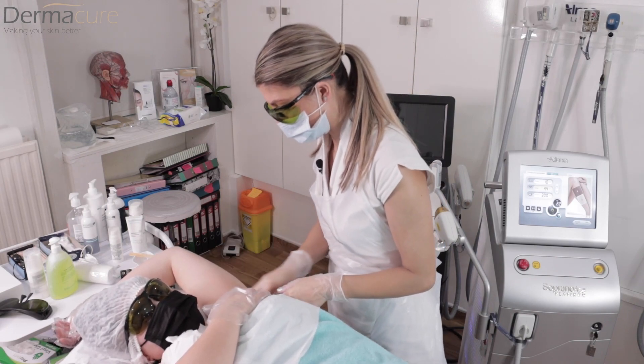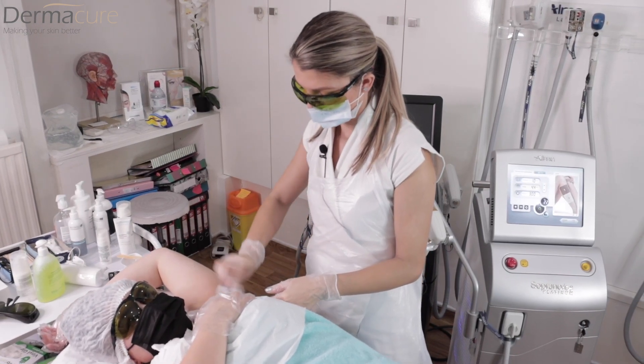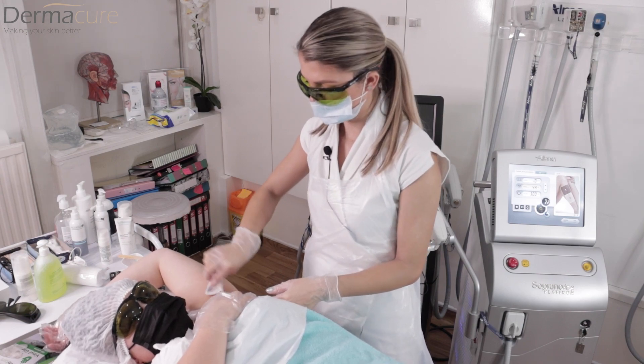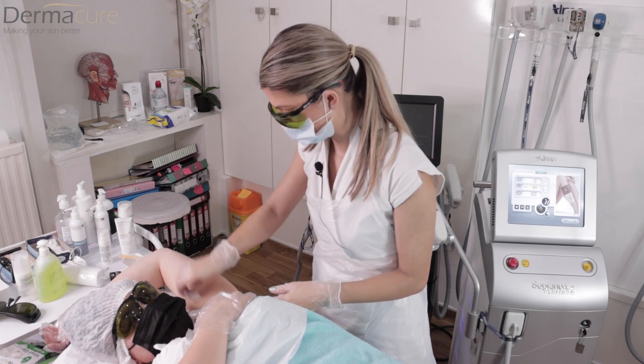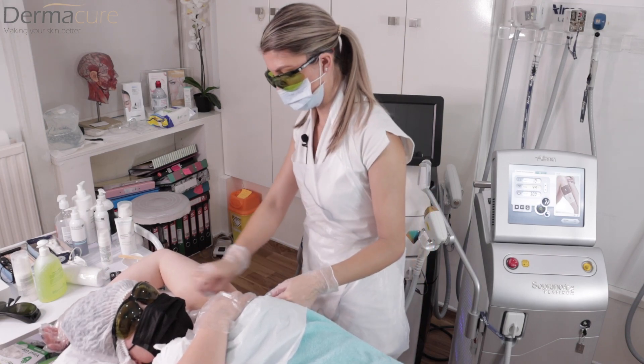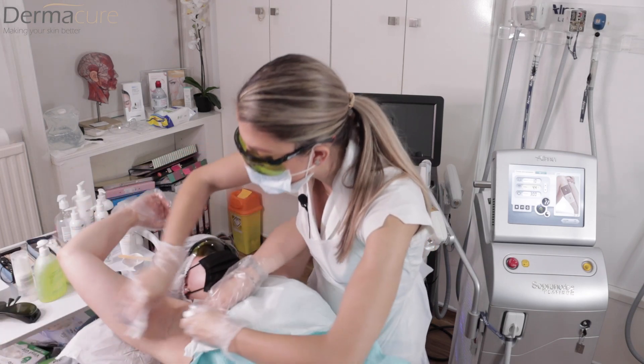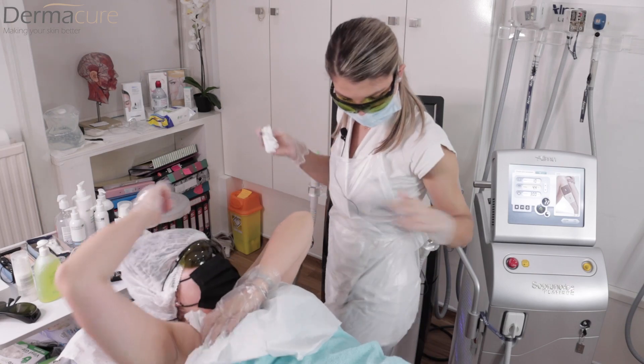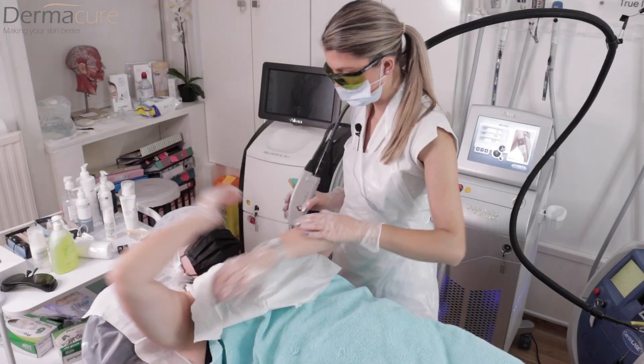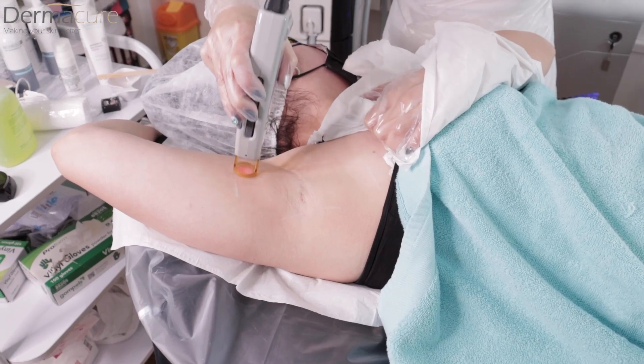For example, when treating the neck or face, clients may have sprayed perfume, which is very attracting for the laser. You need to make sure all alcohol is removed — alcohol and laser light is not a good combination. I'll wipe the other area as well and then mark those areas. Jewelry is not a problem.